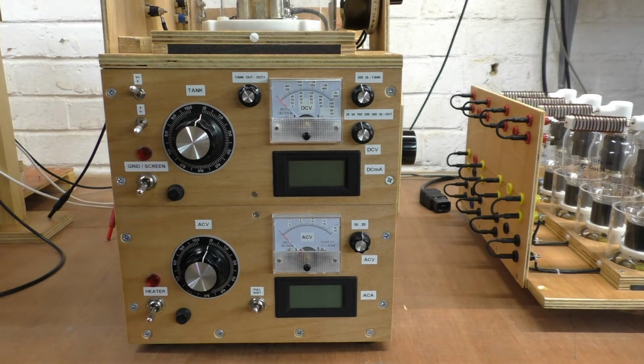Internally, there is a ground reference switch, which determines whether the negative output, the black terminal on this unit, is connected either to the centre tap or to the lower end of the lower secondary. For example, for a screen supply, you might have that attached to the lower negative end. For the grid supply, where you want plus or minus output, you have that attached to the centre tap. That's an internal setting; there is a switch inside, which I will show later.